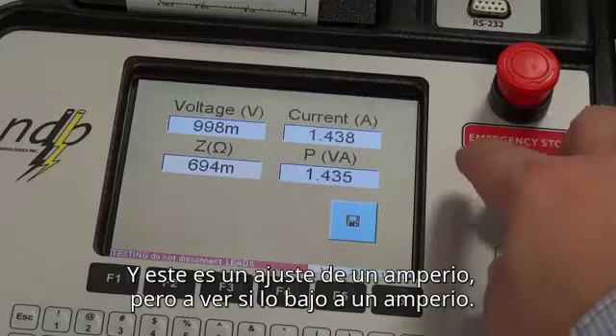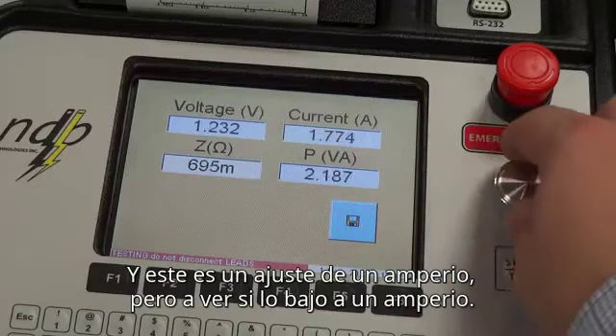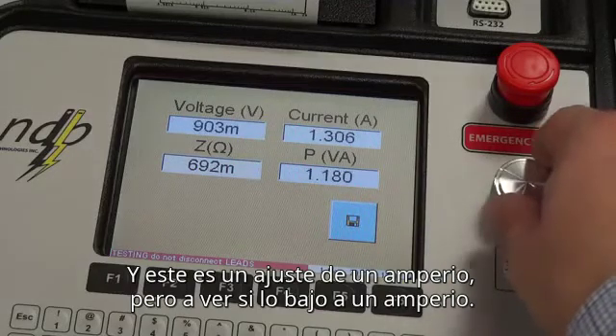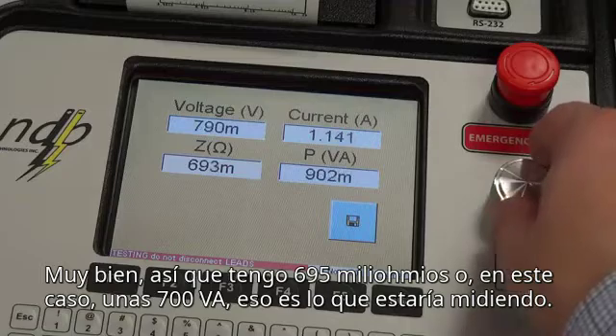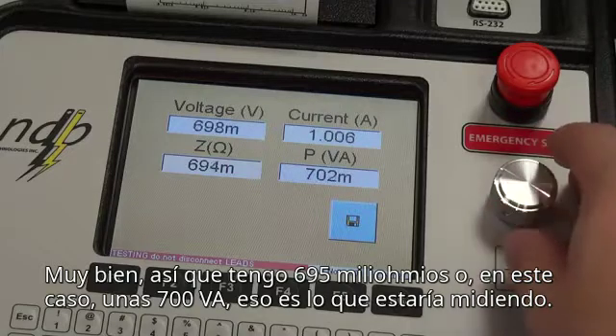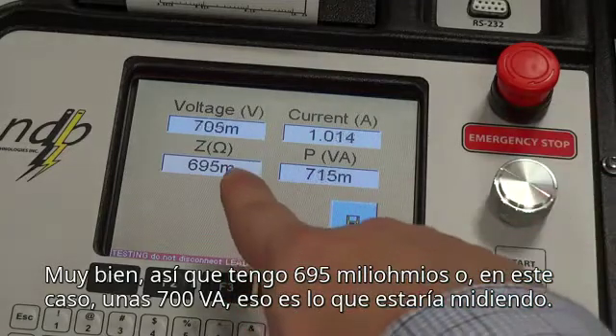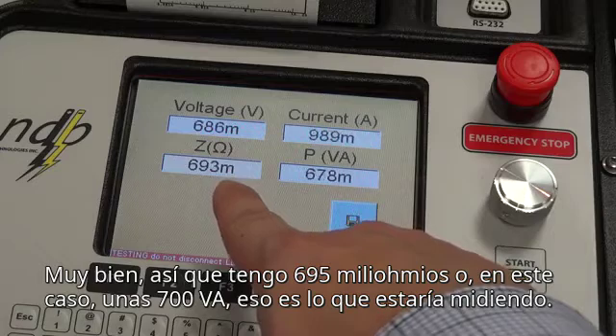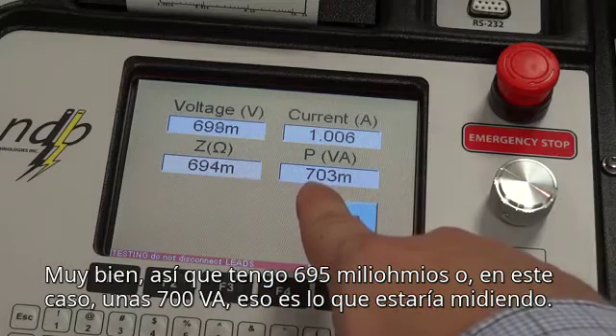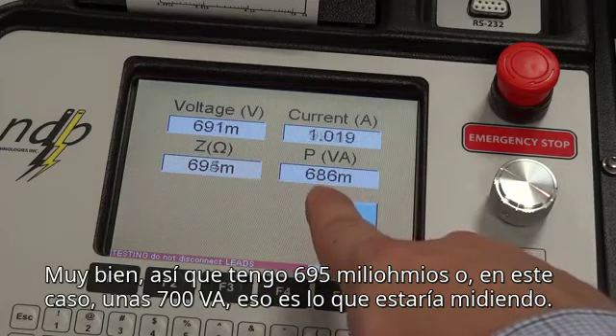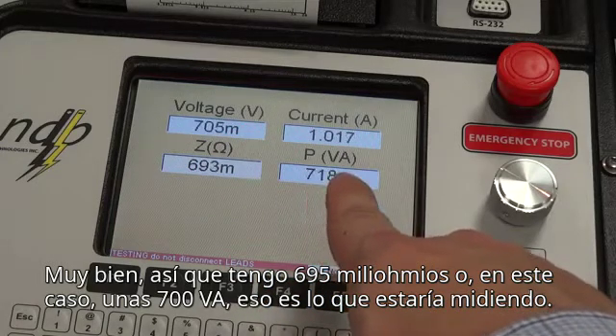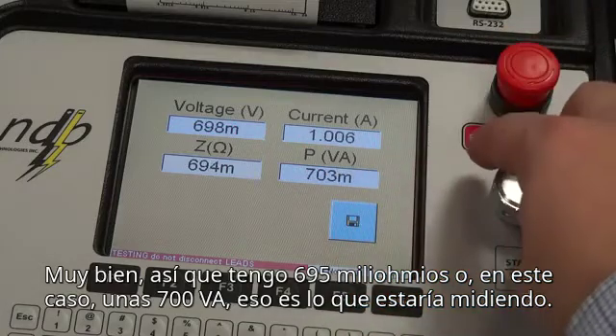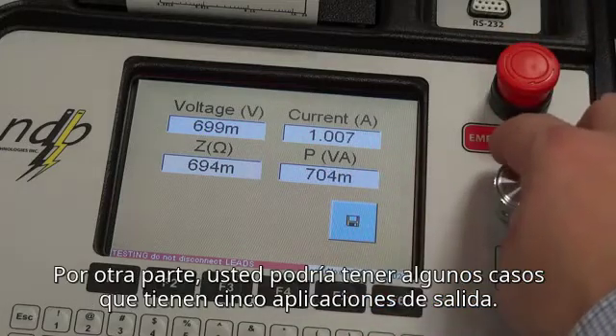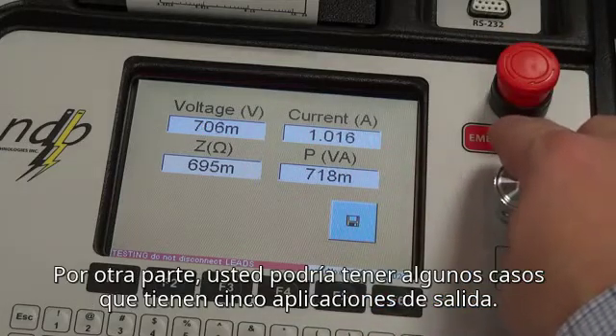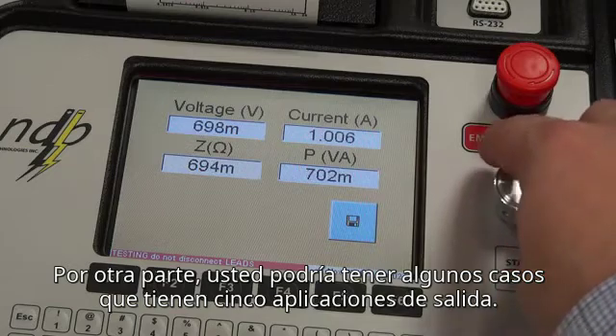This is a 1 amp CT, so if I bring it back down to 1 amp, alright, I'm having 695 milliohms, or in this case, roughly 700 VAs. That's what I'd be measuring. This is simulating the load that the CT would see.